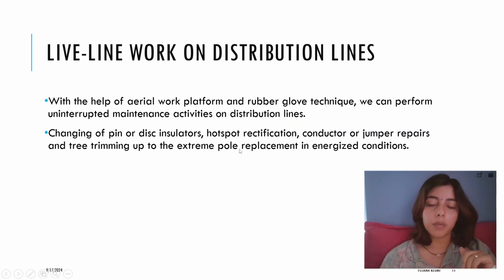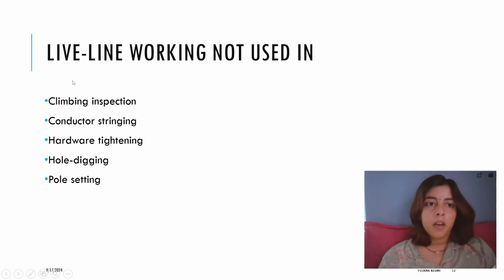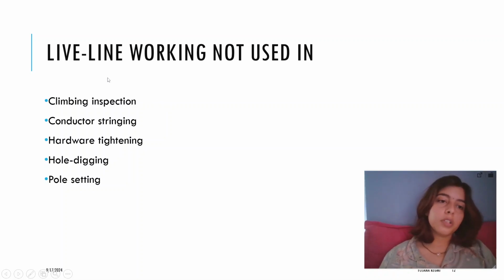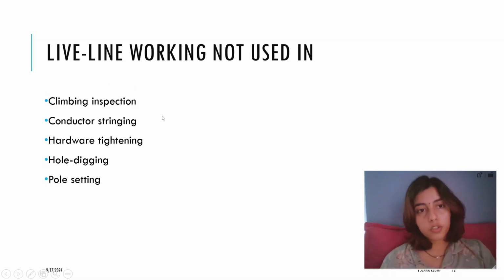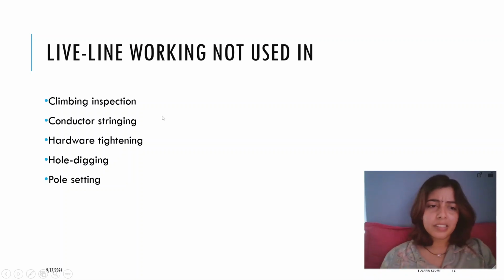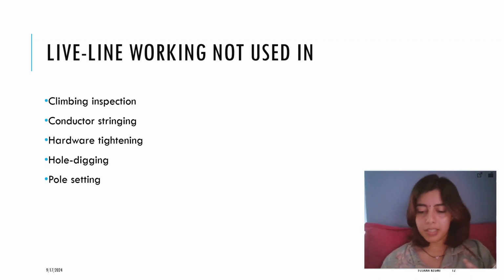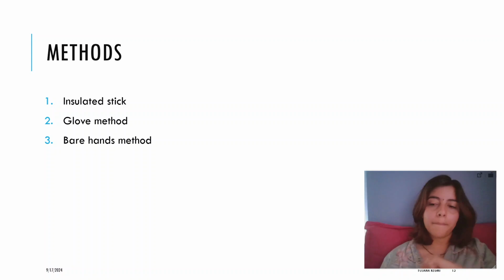We can even replace a pole in the energized condition, but there are techniques and regulations to follow for all these. There are some scenarios where we're not going to use live line working, for example climbing inspection, conductor stringing, hardware tightening, hole-digging, and pole setting. So live line working can't be used everywhere.